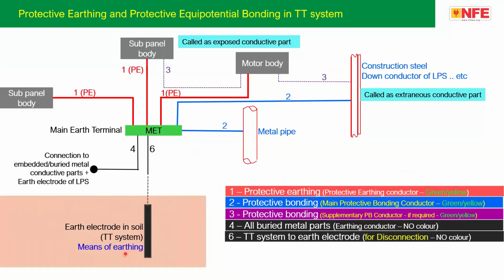A TT system is practically applicable for low voltage public electricity distribution; it is not applicable if you have your own transformer or your own DG set. So you can also go for a TT system. In the case of a TT system, you can see here the exposed and extraneous conductive parts are connected to the MET, and the MET has to be connected to the earth electrode in soil, and this is called the means of earthing. Often, if you look at the standard, it's written that metallic water supply pipes or gas pipes shall not be used as the sole means of earthing.